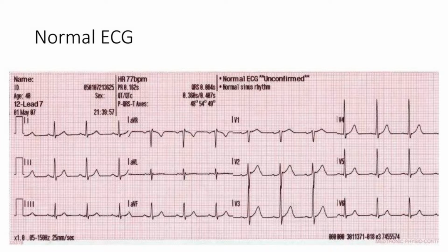Generally, you want to ensure that when you do your ECG, you make sure the leads are well positioned. You do not want to filter. Tampering with the filter settings should be a last resort, because there are implications to tampering with the filter settings.